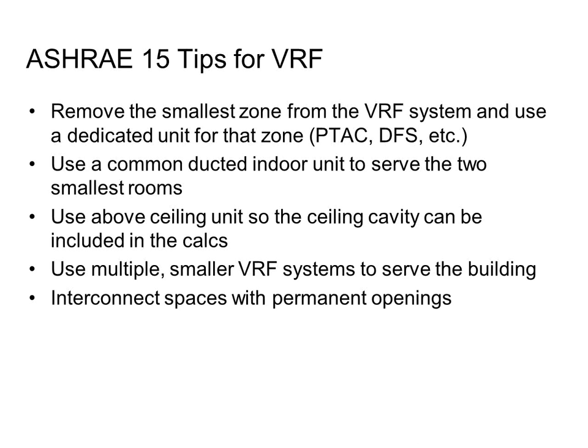Now, just to be clear, they don't say whether shaving doors down counts as permanent openings, but almost everyone I talked to is in agreement that shaving the door down does not count as a permanent opening, because you don't know what's going to happen 5-10 years from now when they put new doors in and they don't put them shaved down. You're going to be the liable person. So that is not really acceptable as a permanent opening.